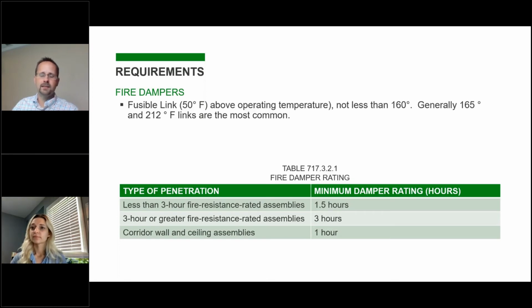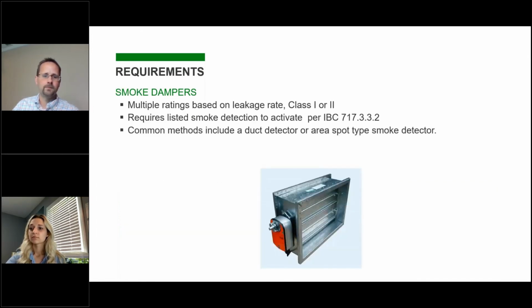But obviously, the fire damper works. There's a spring-loaded either curtain or spring-loaded blades that have a fusible link, and it melts when temperature gets too high, and that's how it closes. Very, very simple. The only thing is you have to coordinate the fusible link with the temperature of the air. But fortunately, unless you're in industrial applications, it's going to be pretty consistent most of the time. Not something that we have to think about on a project-to-project basis. And again, coordinating what damper is installed with the rating of the wall assembly. That's usually kind of an automatic thing, but you want to make sure that things are not misapplied or that dampers rated for a lower rating are not installed in the wrong wall.